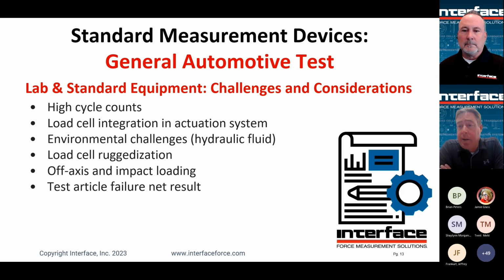Impact loading is also one that gets folks in trouble from time to time, where they don't know or can't control how hard an impact is. And a lot of times that impact force ends up being a lot higher than what is anticipated. So it's important to know that the duration of the event is not so much the problem, it's the amplitude. It doesn't matter how long the load cell is subject to a load, it's what that peak amplitude is, and it has to be within the safe overload rating of the load cell. And of course, that off-axis rating also comes into play there, as it effectively lowers that safe axial. And we'll touch more on that later on.